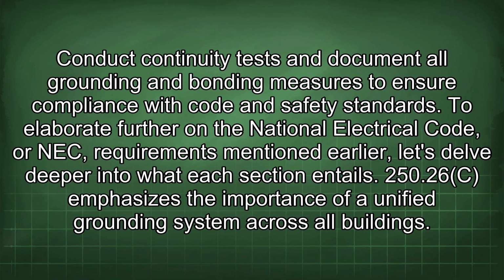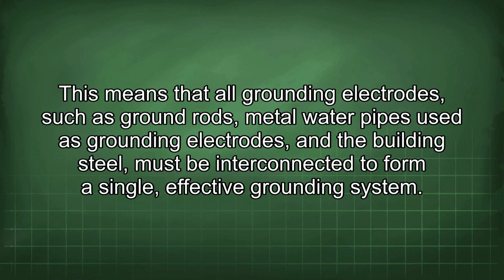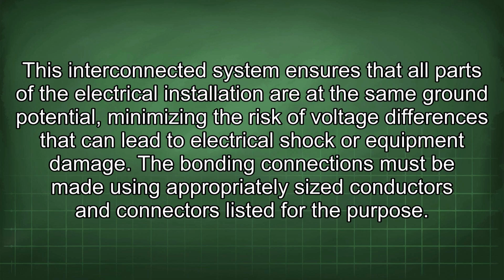250.26c emphasizes the importance of a unified grounding system across all buildings. This means that all grounding electrodes, such as ground rods, metal water pipes used as grounding electrodes, and the building steel, must be interconnected to form a single, effective grounding system. This interconnected system ensures that all parts of the electrical installation are at the same ground potential, minimizing the risk of voltage differences that can lead to electrical shock or equipment damage.